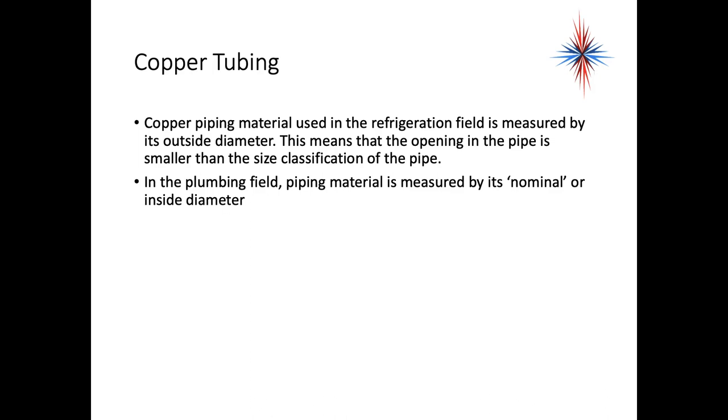In the plumbing field, piping material is measured by its nominal or inside diameter. So again, for ACR piping that we use in refrigeration and air conditioning, it's measured by its outside diameter. Plumbers measure material by its nominal or inside diameter.